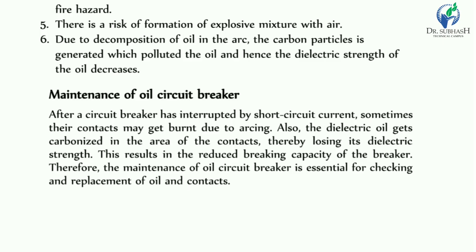During short circuit current interruption, contacts may get burnt during the arcing. Also, the dielectric oil gets carbonized in the area of contact, thereby losing its dielectric strength. This results in the reduced breaking capacity of the breaker.